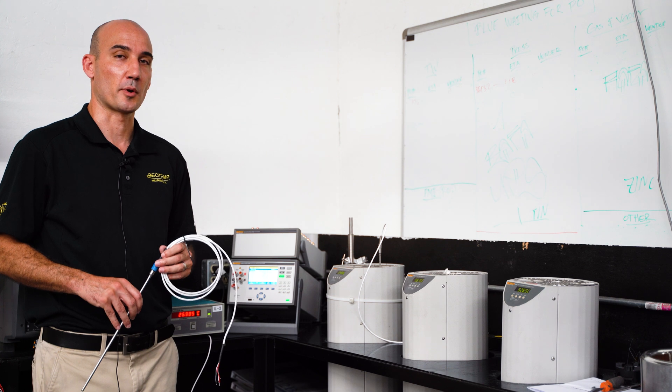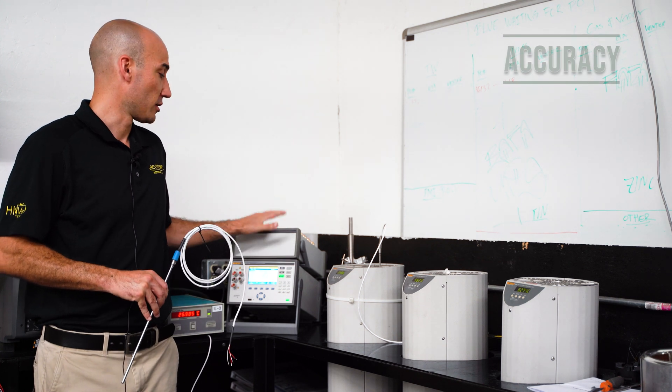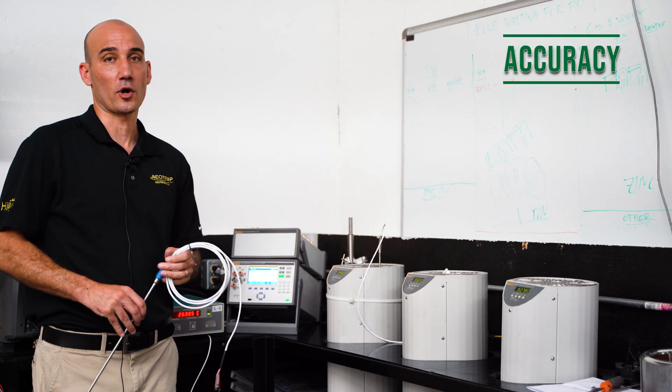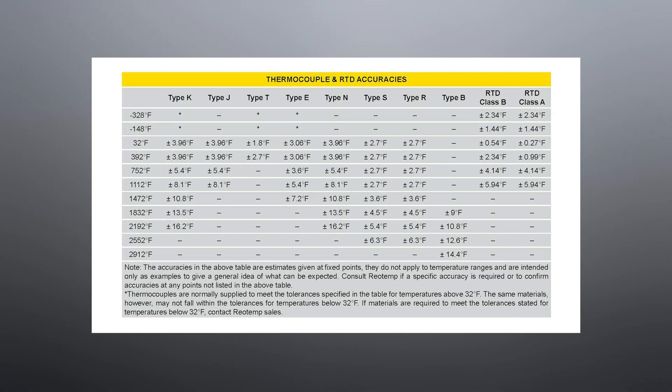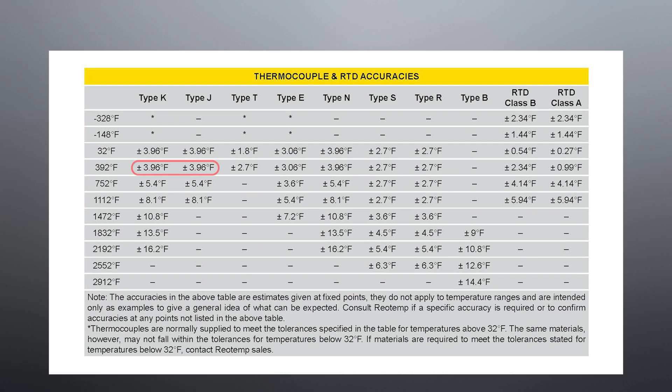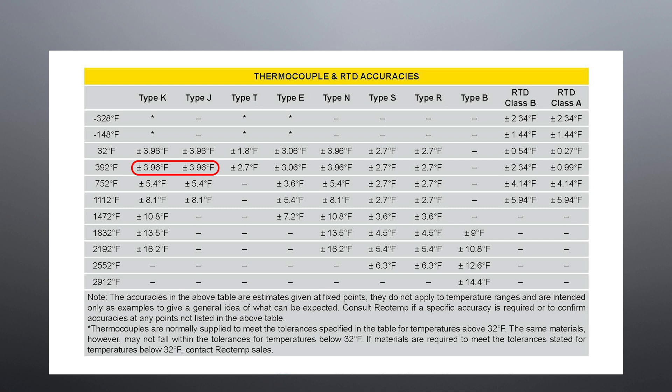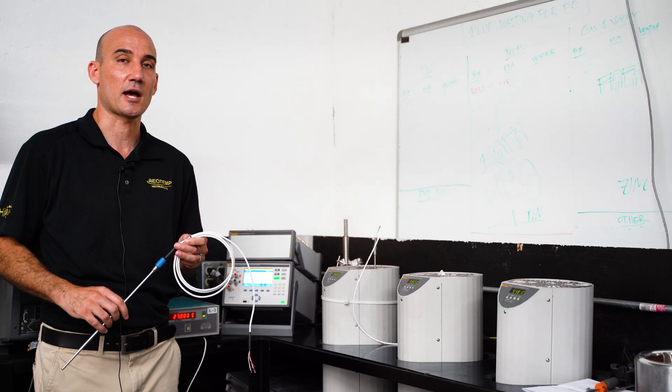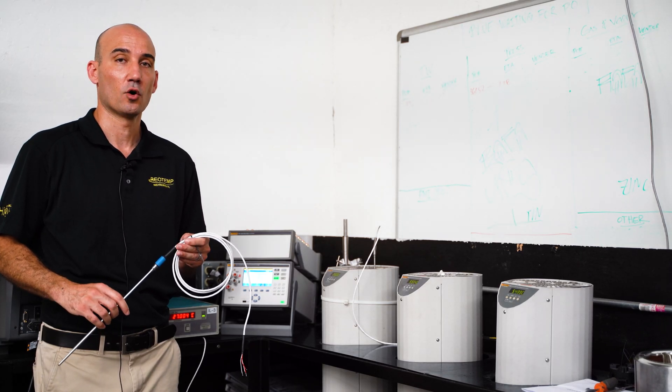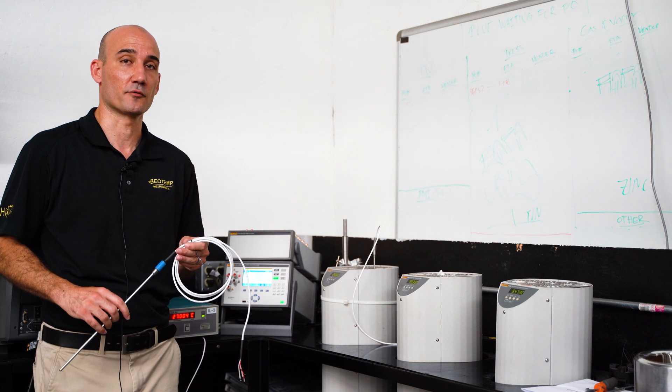Another critical comparison is accuracy. As a general rule, RTDs are more accurate than thermocouples. This is especially true at lower temperatures. If accuracy, linearity, and repeatability are your primary concerns, RTDs are a good choice. If you require better accuracy than what you see here, check out the high accuracy option for RTDs or the special limits of error option for thermocouples.